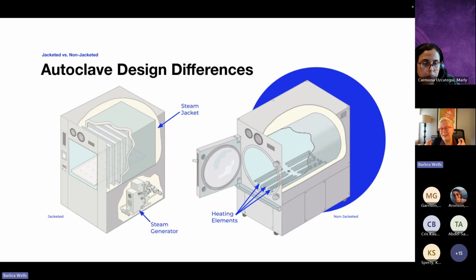You can see the integral steam generator on the left sitting under that chamber, ready to pipe steam up into the jacket, and some electric heating elements in the bottom of the chamber on the right. The non-jacketed autoclave is on demand, so when it's time to run a cycle you have to turn it on. There is no standby mode. Water fills the bottom of the chamber just enough to cover those heating elements, and voila, steam on demand.